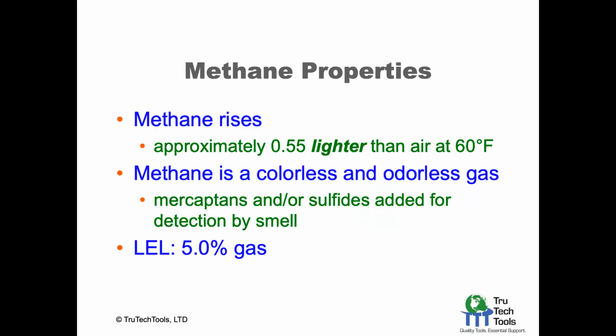So this would be a little hack you should know. If you're measuring a propane leak in a propane system, and you're at the ppm level, you should have the probe below where the source of the leak may be for propane, and above for methane. So if it's a pipe, measure above the pipe for methane, because methane has a tendency to leak out and then rise in the atmosphere. Propane will actually do the opposite: it will leak out and drop in the atmosphere.